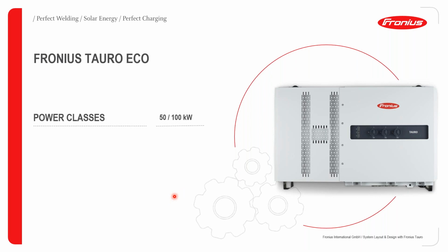The second variant of the Tauro is what we are referring to here as the Tauro Eco, and the Tauro Eco is available in the power classes 50 and 100 kilowatts. The MPP operational range for the Tauro Eco will be 580 to 930 volts.